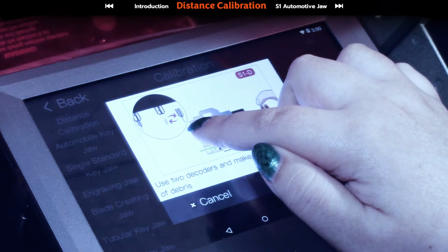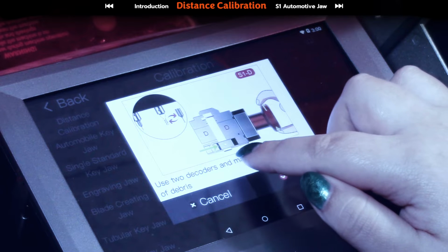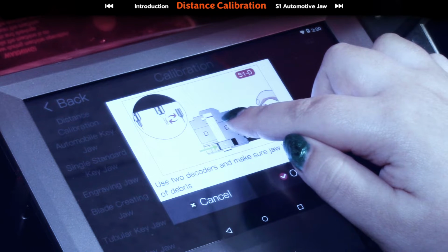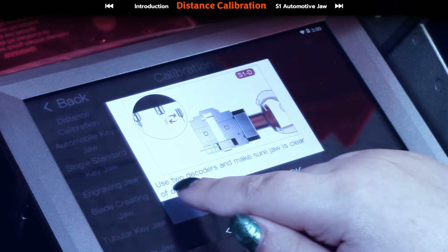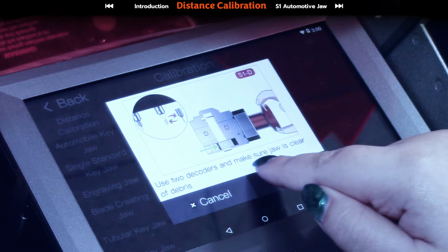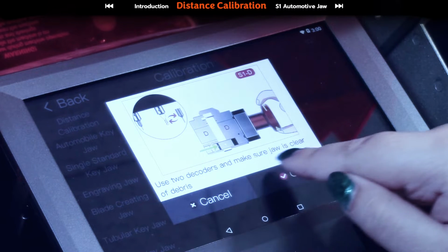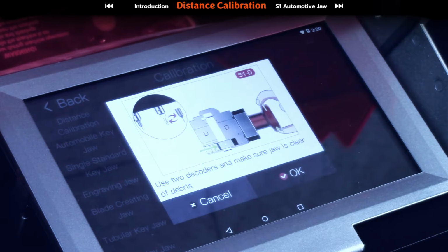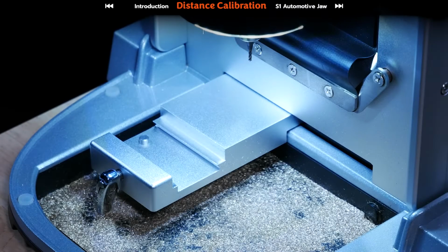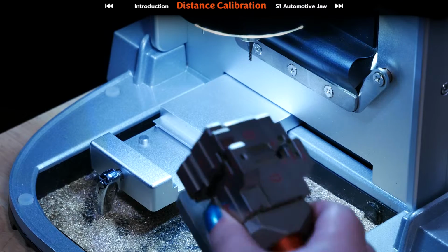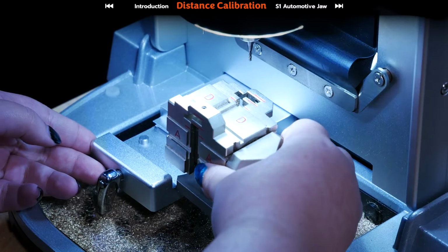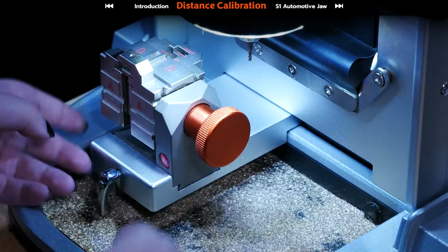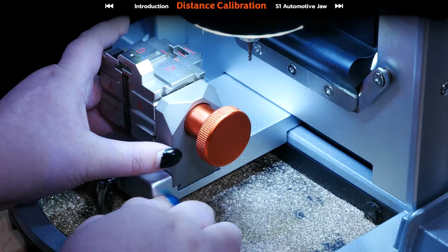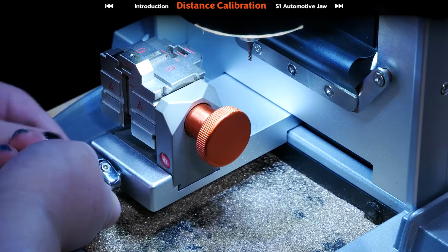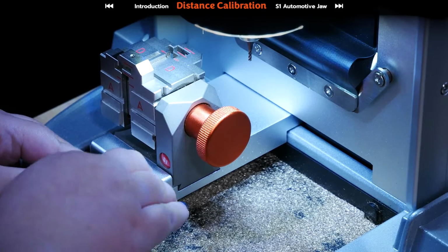As you can see right here, we need to switch out our cutter for a decoder, and then we need to use the calibration block and insert it to the middle red line. It says here, use two decoders and make sure jaw is clear of debris, and that is going to be before we start the calibration. So now we're going to grab our jaw and we're going to go ahead and slide it in. Make sure it is nice and leveled. We don't want it to be at an angle. And then we're going to lock it in place.